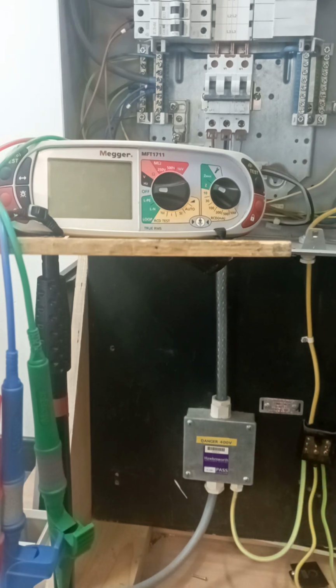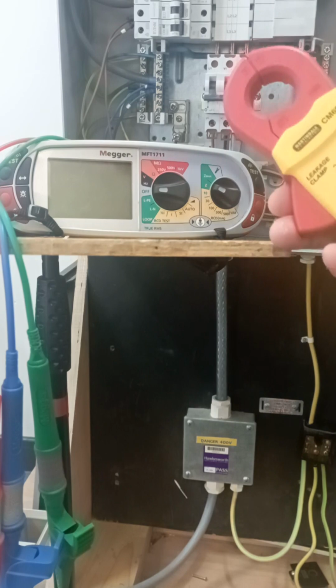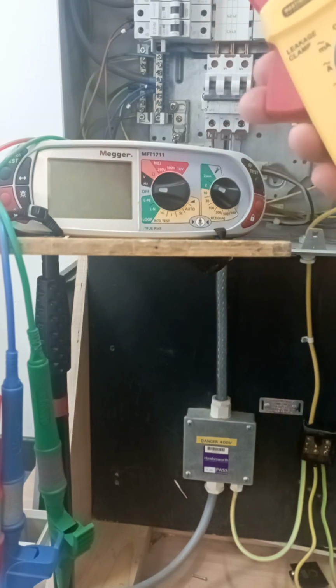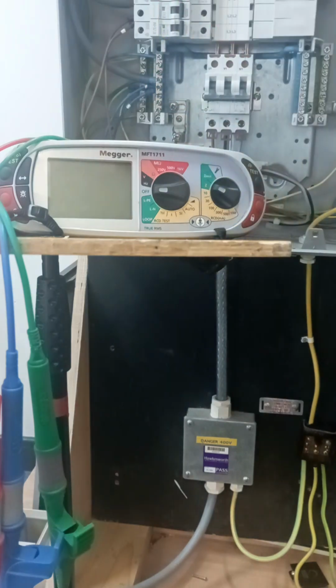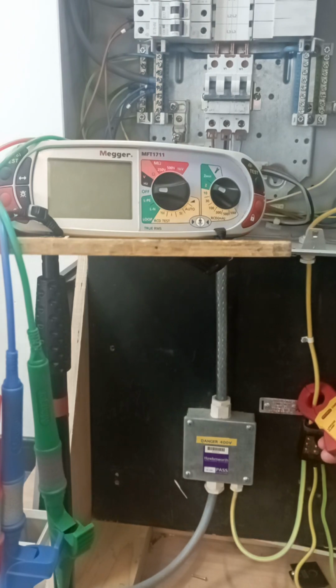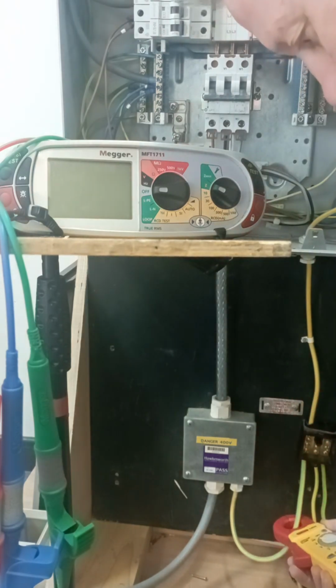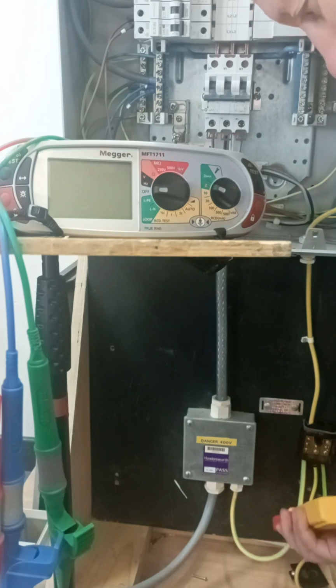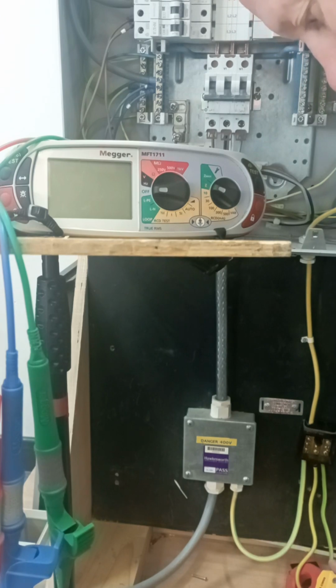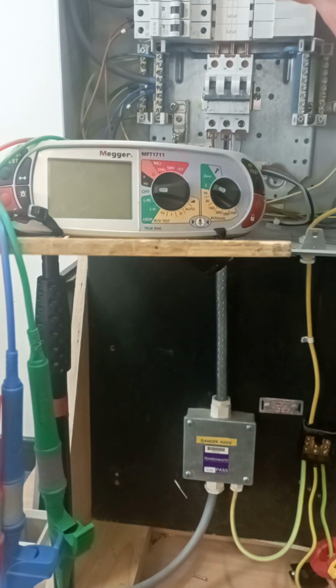Now obviously, prior to disconnection, with the installation shut down as opposed to isolated yet, we get our current clamp meter and clamp all of the conductors going in and out of the main earthing terminal to see if we have any current flowing. You'll see that it's all dropping back down to either 0.00 milliamps or 0.1 milliamps.